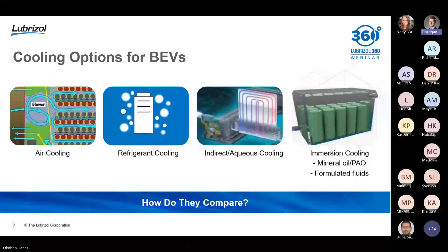The water glycol systems are efficient, but again, the indirect nature of it, the fact that it's removed from covering the entire surface area of the cell and the thermal resistances associated through the pack material as well as the cold plate, leaves some performance to be desired within this system. So we move into the immersion cooling system again, which is what we're focused on today.